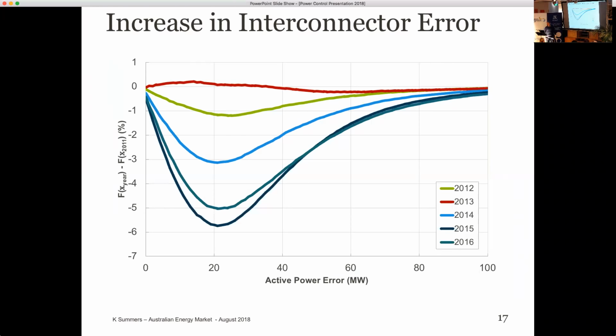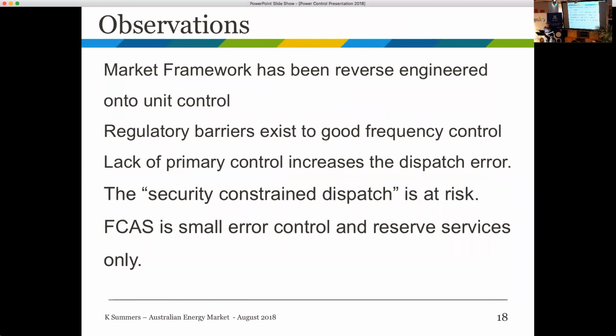So our observations: the market framework has been reverse engineered onto unit control. There are regulatory barriers that exist to good frequency control. There's a lack of primary control, which increases our dispatch error, and our security constrained dispatch is at risk. The FCAS services we have are only small error control and reserve services. They are not primary frequency control, because when we created that market, we assumed that synchronous machines would maintain their governor control.